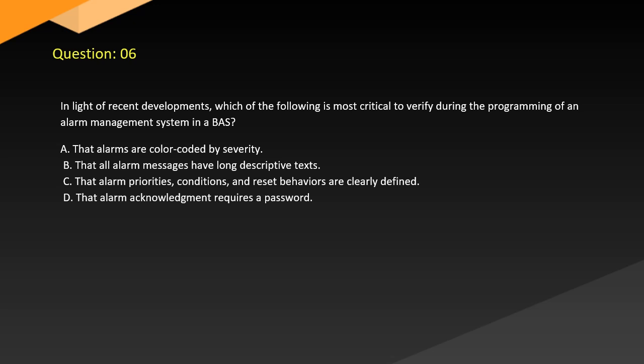Question 6. In light of recent developments, which of the following is most critical to verify during the programming of an alarm management system in a BAS? A. That alarms are color-coded by severity. B. That all alarm messages have long, descriptive texts. C. That alarm priorities, conditions, and reset behaviors are clearly defined. D. That alarm acknowledgement requires a password.